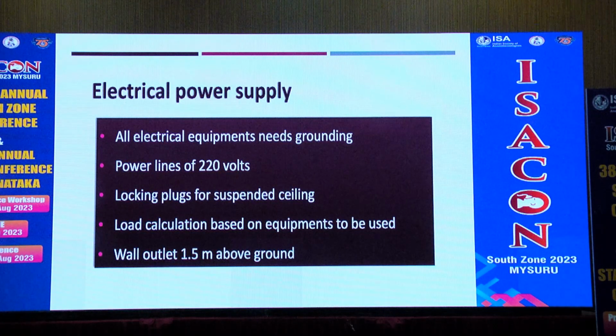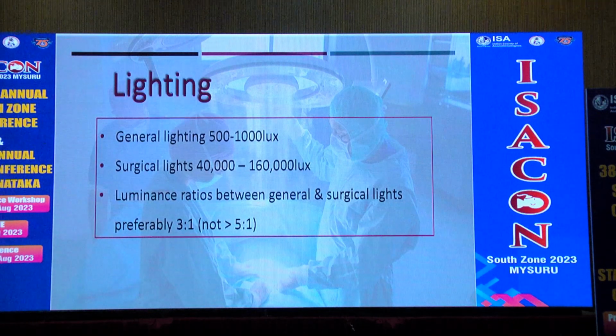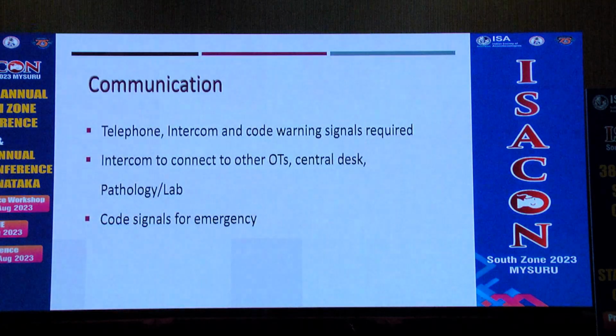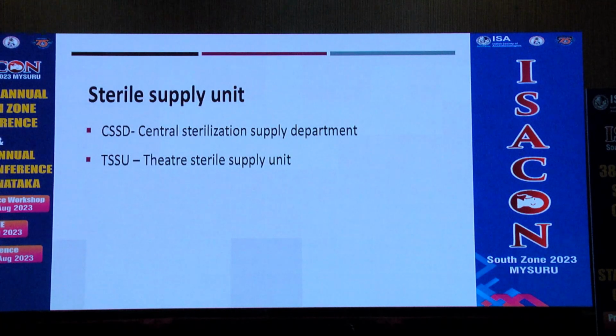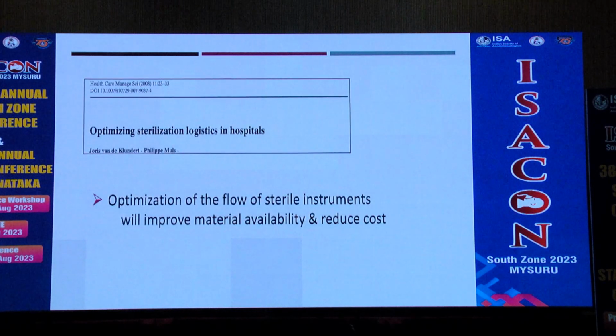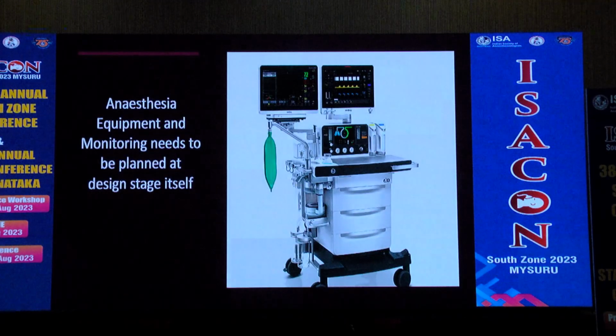Coming to the electrical supply, all electrical equipment needs adequate grounding and the power line should be 220 volts. The suspended ceiling plugs should be of locking type and the load should be calculated on the equipment used. For lighting, depending upon the surgeon, there are also specifications. For communication, there should be an intercom to connect with the other OTs, central desk and lab service, and code signals for emergency. For sterile supply, either a direct connection to the central sterilization unit or to the TSSU. The sterile equipment flow should be optimized to improve material availability and reduce cost.